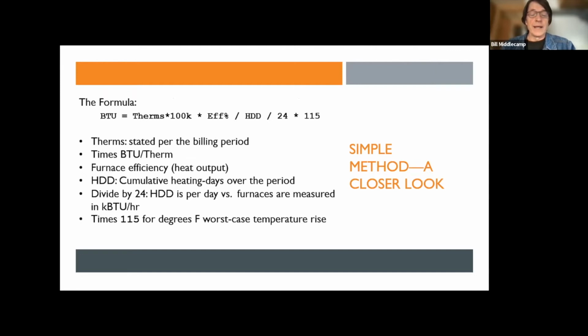So again, a little closer look at this formula. The therms are stated in the bill, and it tells you how long the period is. And then, of course, you multiply it times 100,000 BTUs per therm. You have to understand your furnace efficiency, and there's a lot of factors that can go into that, but you have typically the quoted number from the manufacturer. And a standard efficiency furnace is 80%. I believe that's a law.